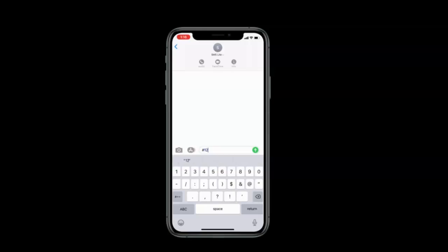If the SMS Lite is connected to a device such as a float switch, which can switch on and off several times before settling, you will need to program in a delay. This will mean the device must stay in the state for the programmed amount of time before the SMS Lite will send a text message alerting you of a status change. The delay is configurable and you can select one of the following options: 0, 5, 10 or 30 seconds, or 1, 5, 10 or 15 minutes. Please note that the debounce value is global to all inputs and you cannot specify different values for each input.